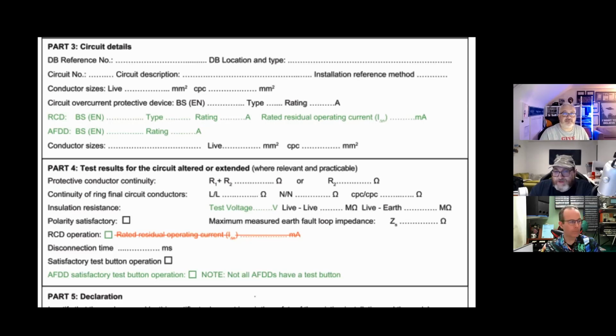Paul's asked why have a tick box for the RCD if there's a tick box for the button below? So he's got RCD operation with a tick box and satisfactory test button operation box. Is the RCD operation box a tick to confirm it's achieved the required disconnection to test? It's a tick box. But you're right, because RCD operation on a lot of devices, like the Electrium one, when you push that RCD test button it will also act as an AFDD checker and get the electronics to do their bit as well. So it seems a bit redundant to have two boxes.